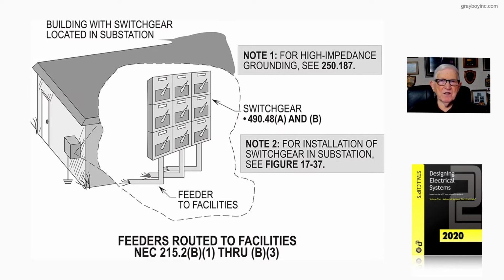Now, basically what this figure is illustrating, feeders routed to the facilities in accordance with 215.2 B1 through B3 when you start calculations and sizing them. Now, one thing you want to point out, and you always want to get with the authority having jurisdiction to do this, but with your mains for the service here in the building located in the substation, this is your service point, so these are feeders going up to each facility, say, or to one facility, however it's arranged.